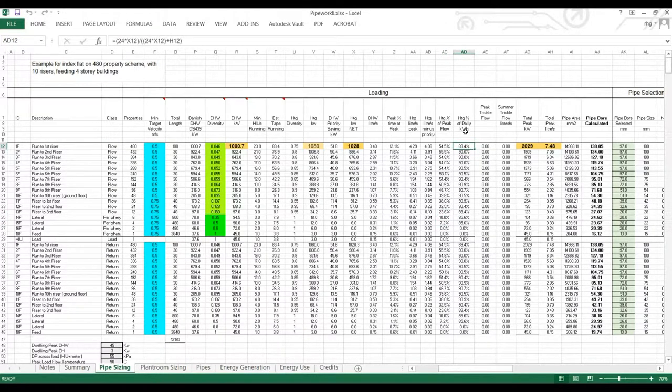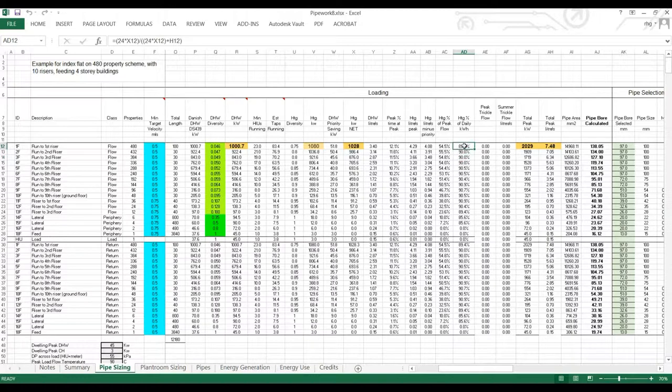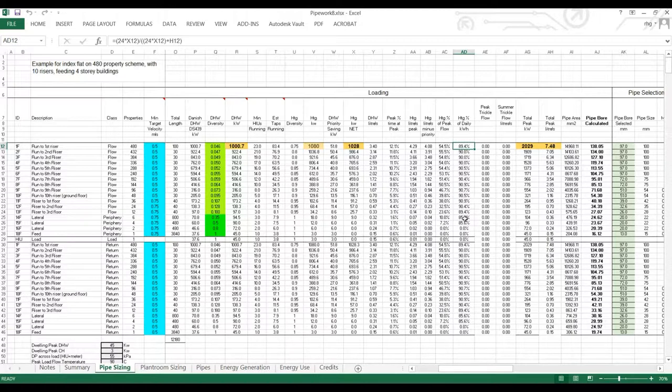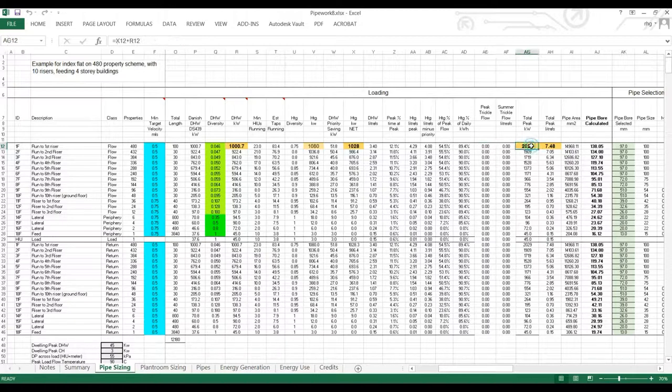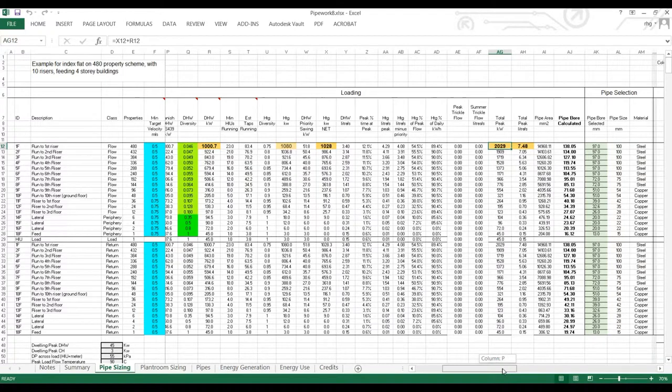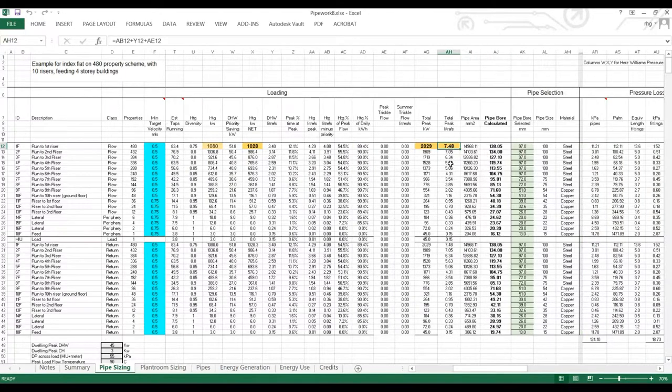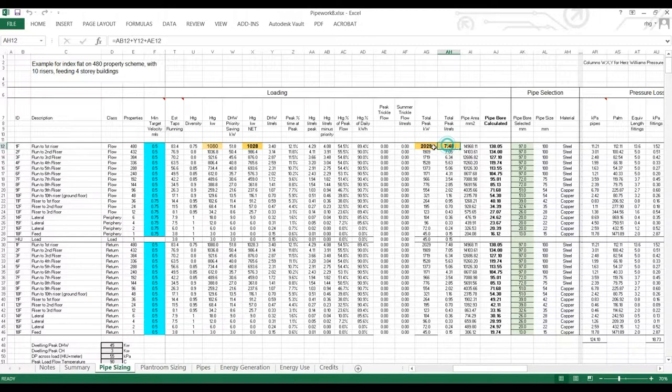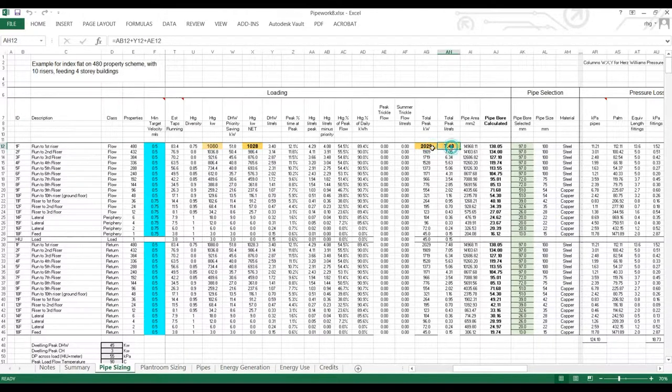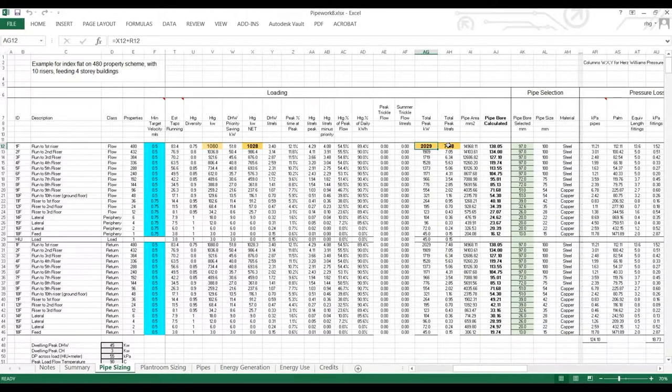Now we have the heating percentage of daily energy use. So this is showing us coming out of the plant room, for the whole site, 90% or so of energy use is going towards driving central heating. The peak trickle flow. Now we've got no trickle flow set in this example, so that's zero. We have the total peak kilowattage, which is the sum of our heating and our hot water loads. We have the total peak flow rate in litres per second from the development. So these two figures allow us to calculate the energy flow and the water flow.